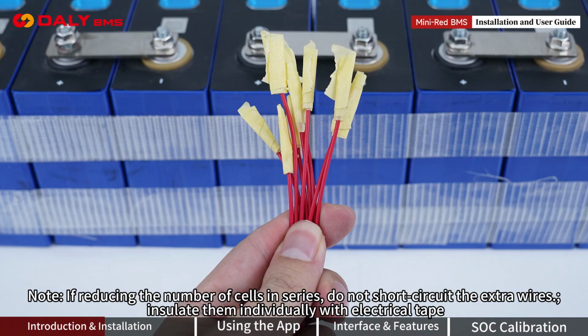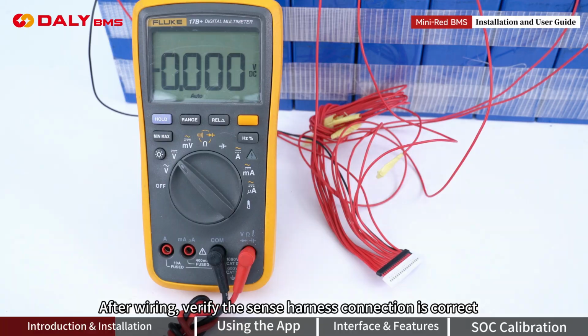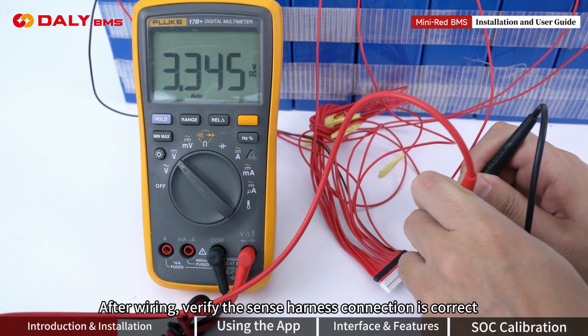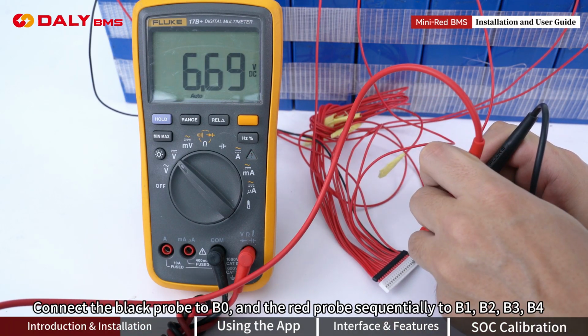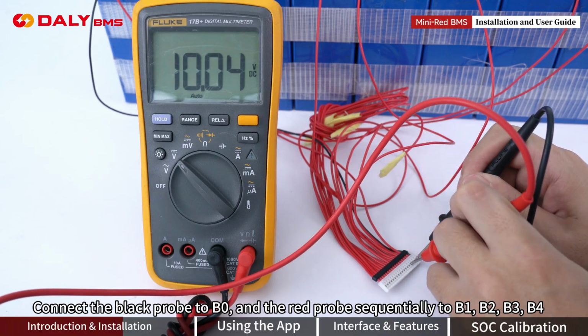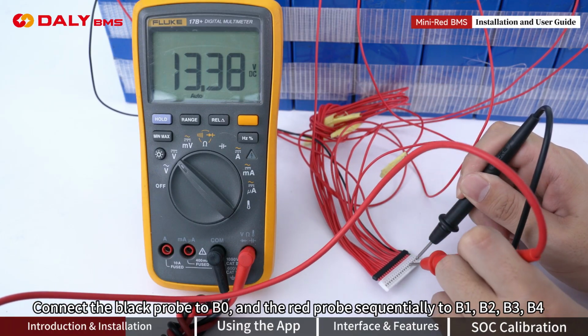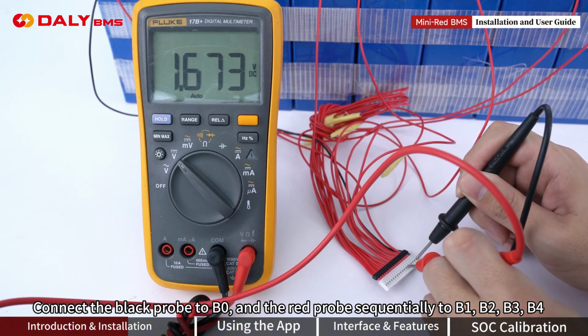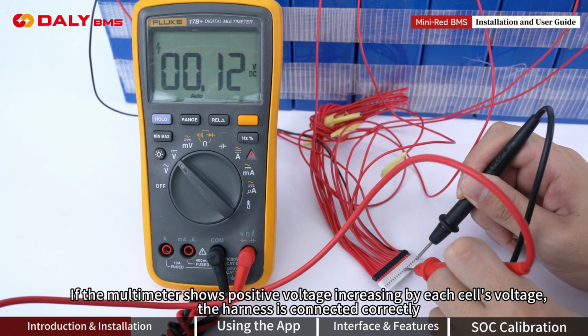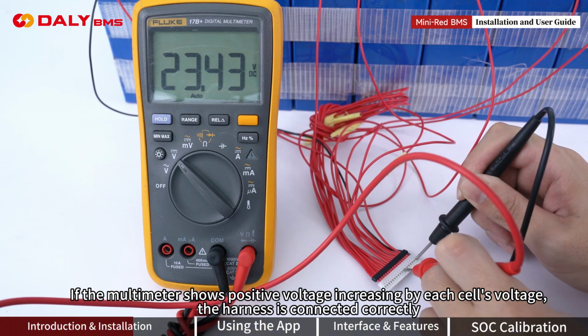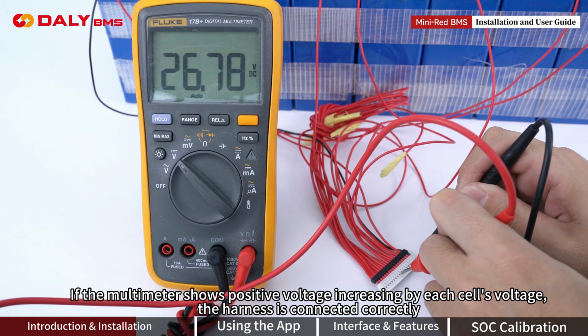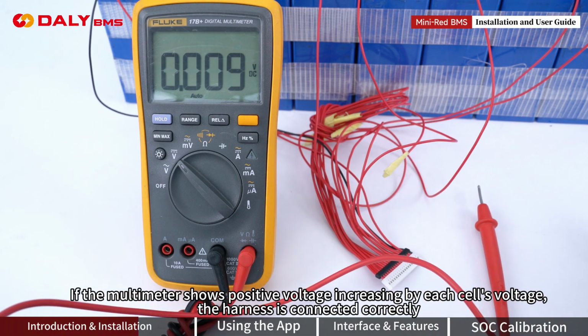Note, if reducing the number of cells in series, do not short-circuit the extra wires. Insulate them individually with electrical tape. After wiring, verify the sense harness connection is correct. Connect the black probe to B0, and the red probe sequentially to B1, B2, B3, B4. If the multimeter shows positive voltage increasing by each cell's voltage, the harness is connected correctly.